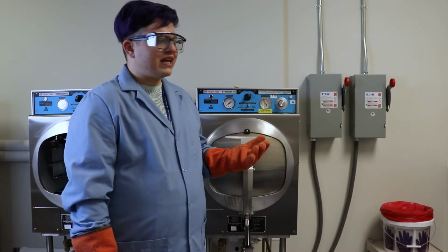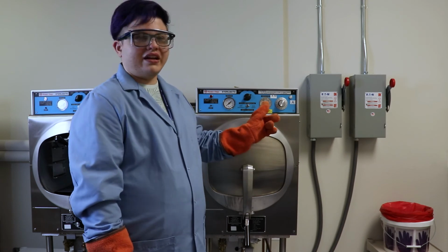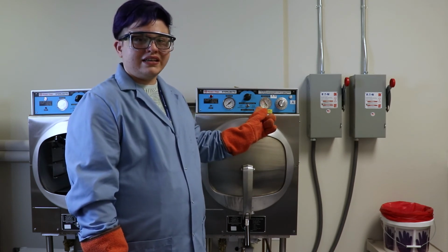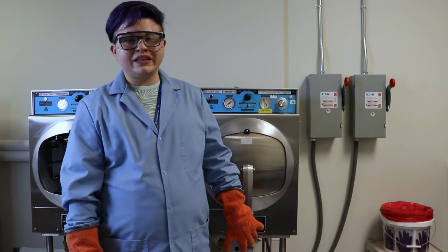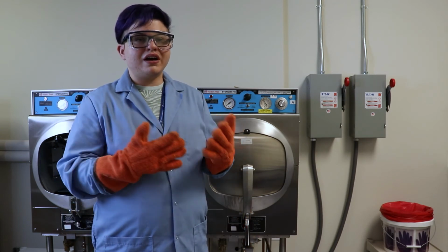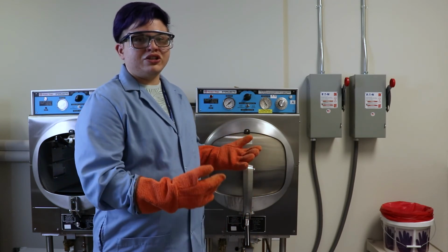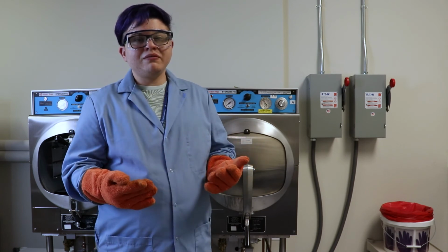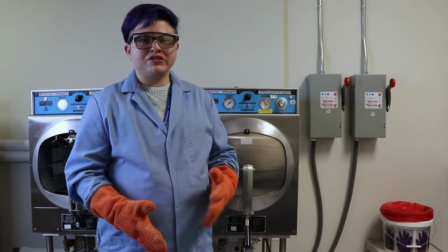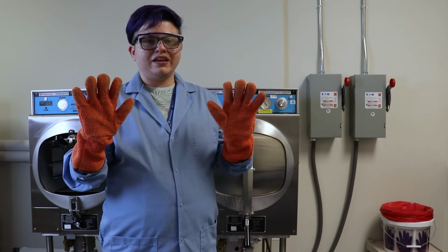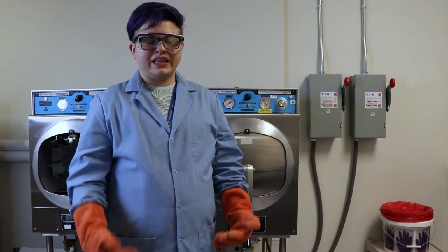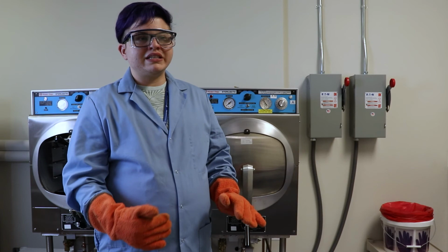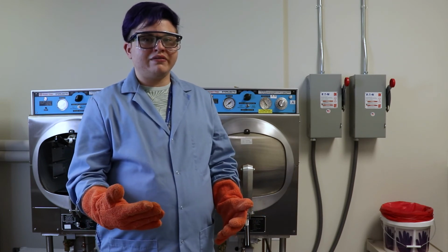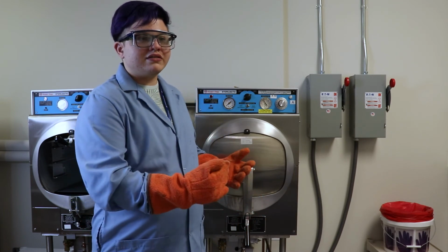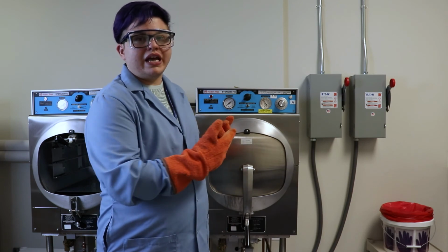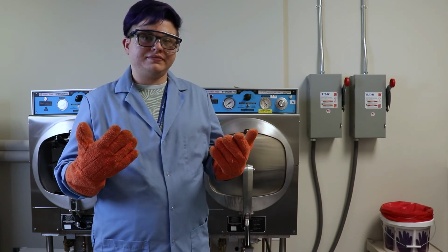Now that the autoclave cycle has finished and we are at 100 C and 0 psi inside the chamber, we are ready to open the autoclave to unload it. Before we actually open it, we want to make sure that we're wearing the proper PPE with the autoclave gloves, glasses, and lab coat. And we want to make sure that we stand as far back from the autoclave as possible, because once it opens, a lot of steam is going to rush out, and we don't want to scald our face.